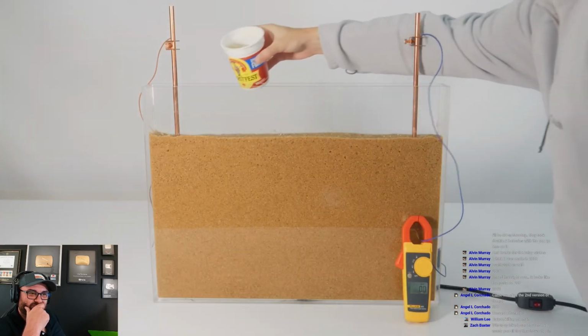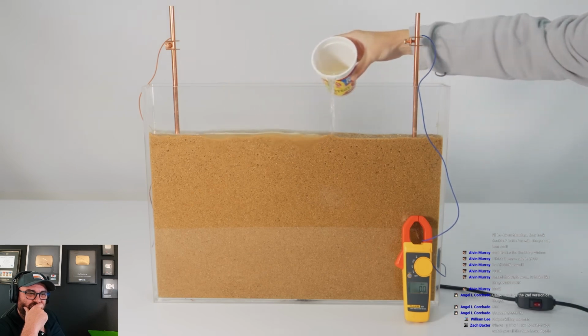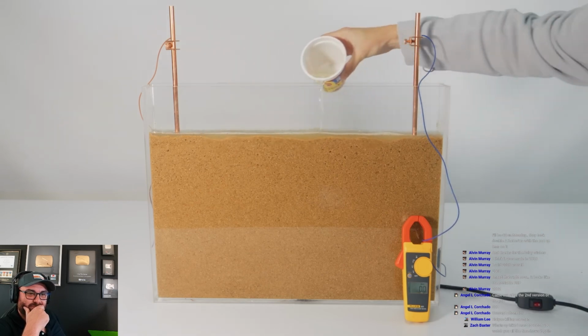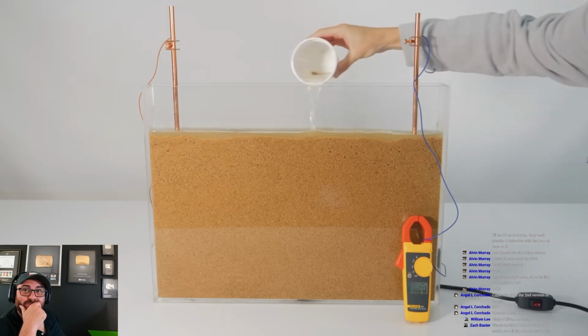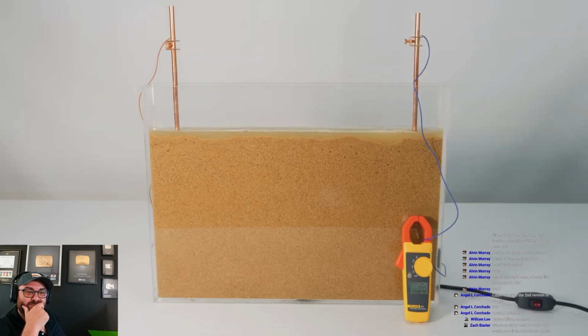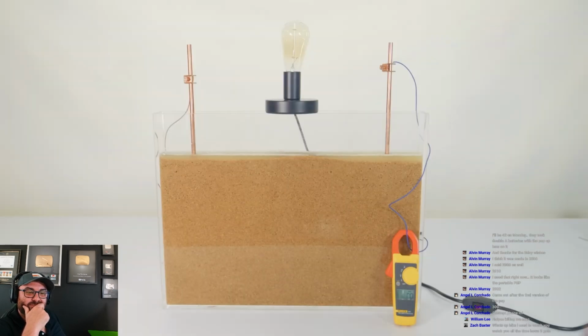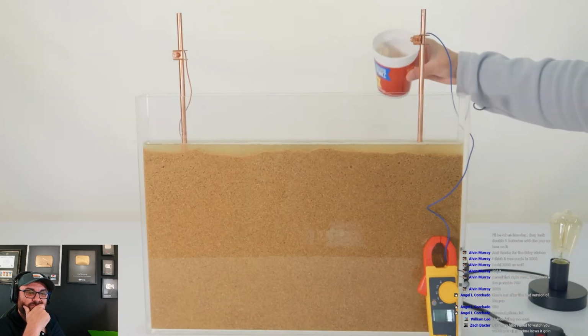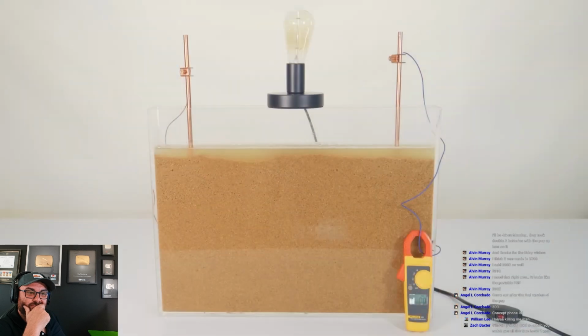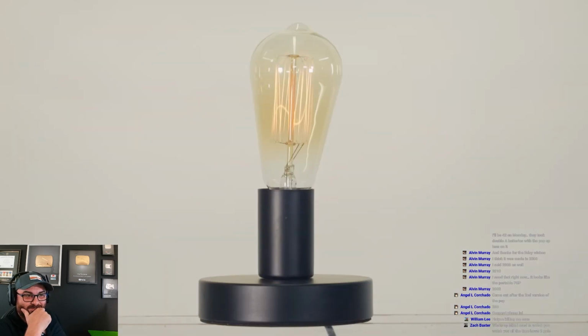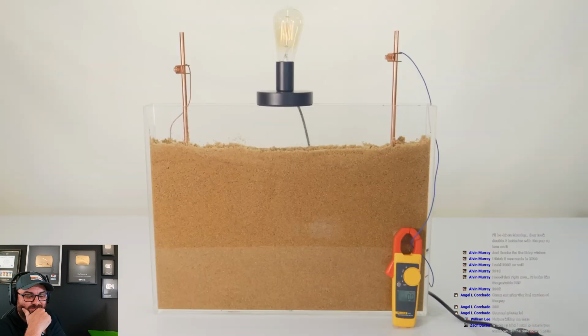Soil resistivity also changes with the chemical constituents in the soil, which is why I'm having trouble getting any current to flow through the sand. There just aren't enough electrolytes. Even with a layer of standing water on top of the sand, it doesn't conduct much current at all. If I add just a little bit of salt water to that standing water, immediately you see the resistivity goes down and the light bulb is able to light. And if I let that salt water soak into the soil, now the sand is able to conduct electricity too.